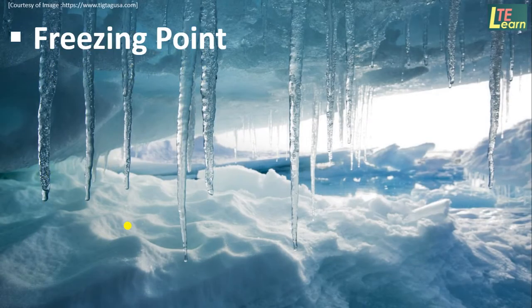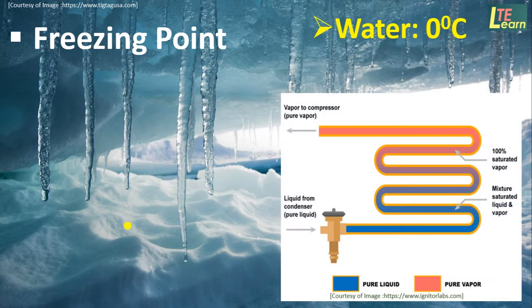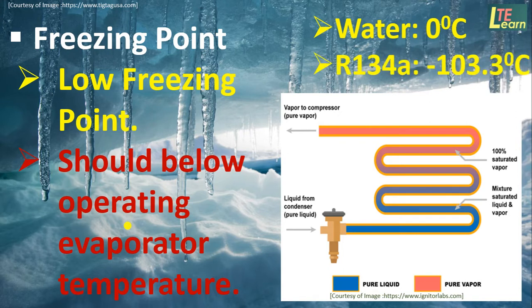Freezing point is the temperature at which the working substance solidifies. As the freezing temperature of water is 0°C, if used in a vapor compression refrigerant system, after expansion the temperature goes below 0°C and it will solidify, making circulation in the cooling coil impossible. Hence, freezing point of refrigerant should be below operating temperature — it should be low. Refrigerant R134A having a freezing point of -103.3°C is used in a domestic refrigerator.